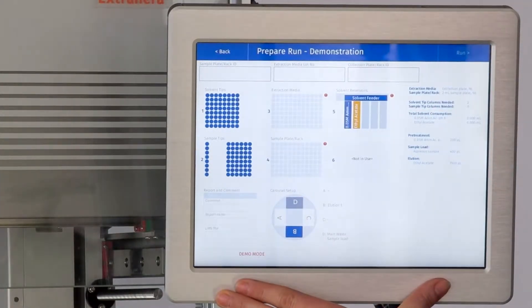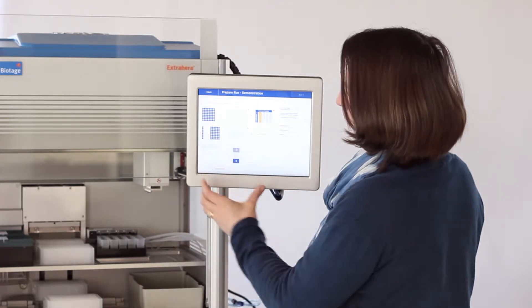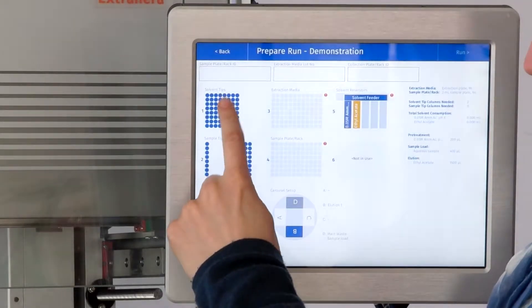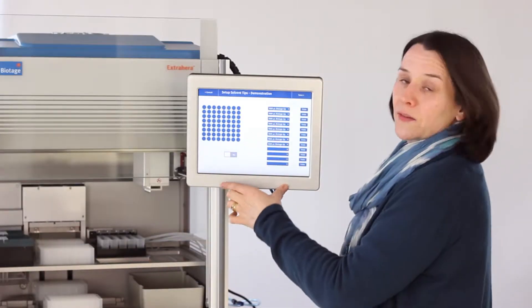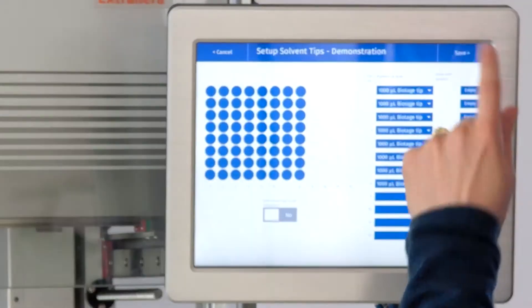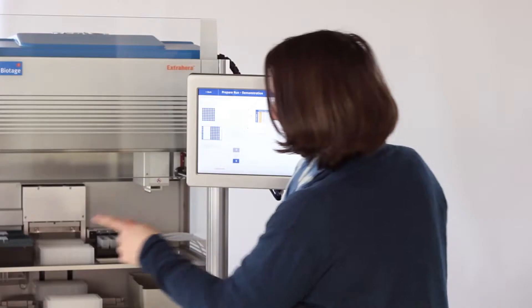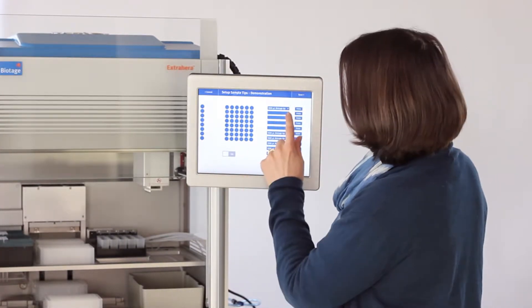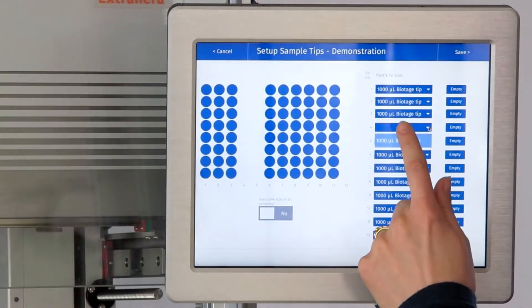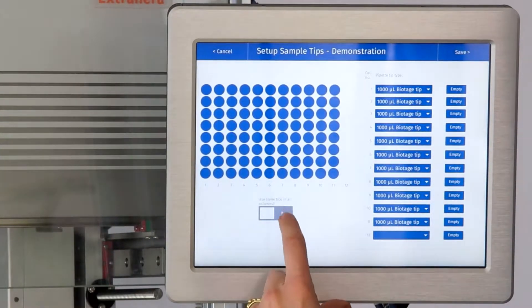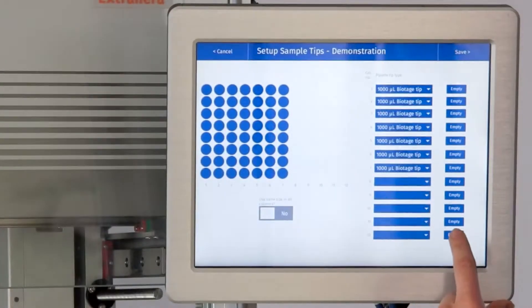This is the screen that shows you what has happened. Now I have moved some of the tips around, so the first thing we're going to do is make sure that the tips that we have in the racks match the tips we have on the screen. So that one is fine but this one is different. If I want to change the tips I just add them on this screen like this, and if you're putting a brand new plate on you can use this toggle button down here. But I've got five rows missing so we'll empty these rows and make sure that this pattern matches what we have here.